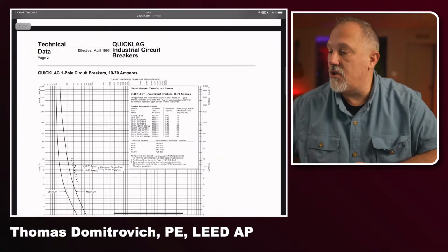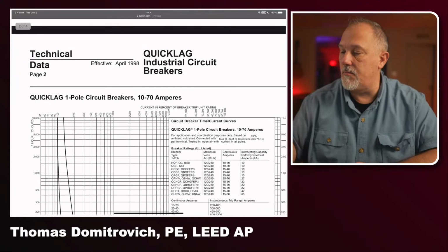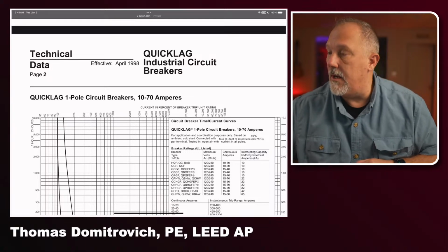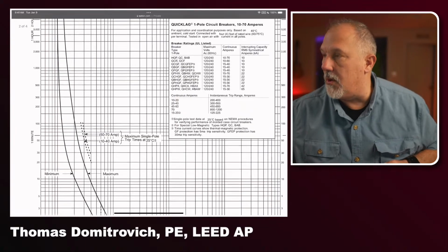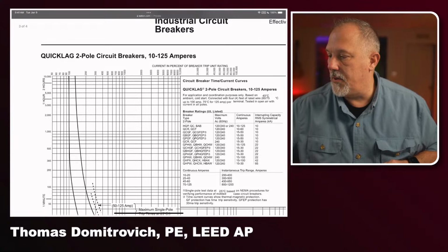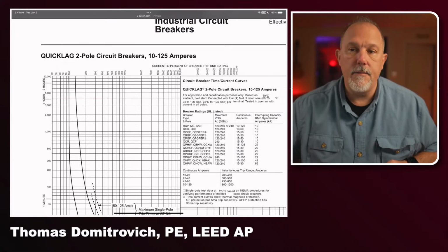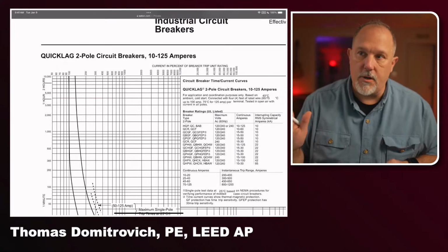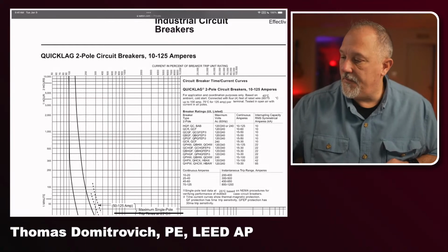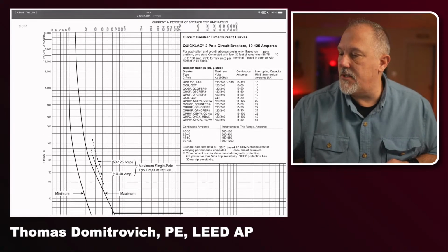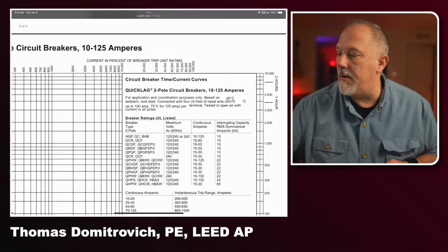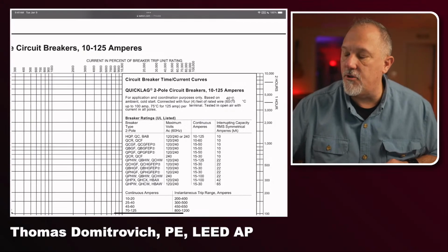These are the trip curves for the circuit breaker that we have pictured there, and that would be a two-pole, a two-pole 10 to 125 amp trip curve. If you look at it, these are all in currents in percent of circuit breaker trip unit rating.